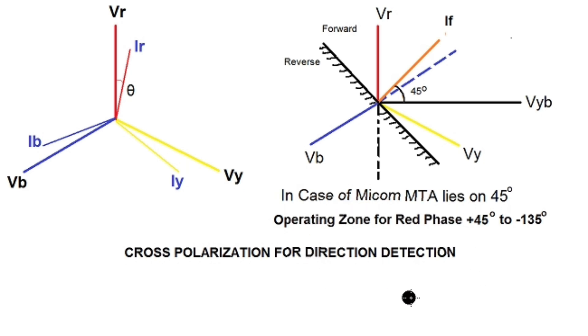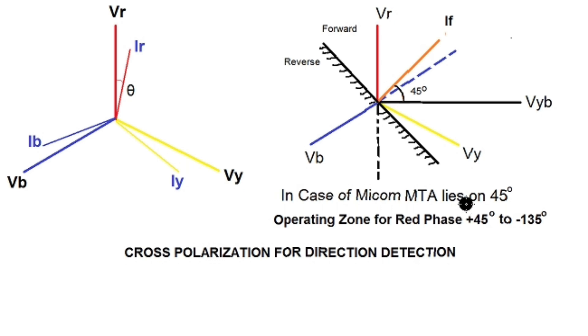How does the directional relay sense direction? In case of overcurrent relay, the directional relay senses direction by means of the cross-polarization method. When a fault occurs in the red phase, the voltage of the red phase will dip, so the healthy phase voltage is used as reference. For a red phase fault, the quadrature voltage Vyb is used as the reference. Vr and Vyb are 90 degrees apart — Vyb lags Vr by 90 degrees.